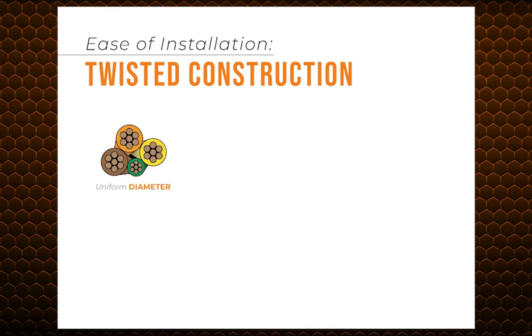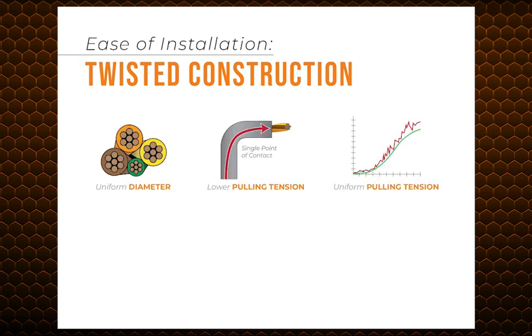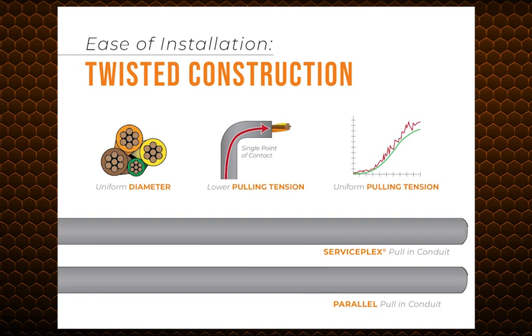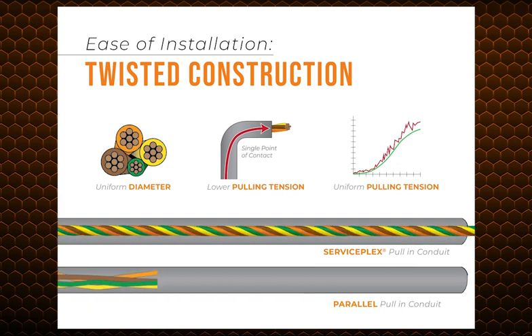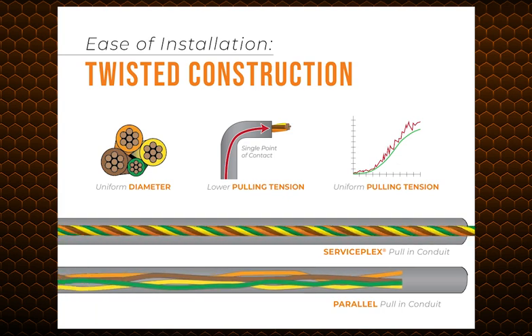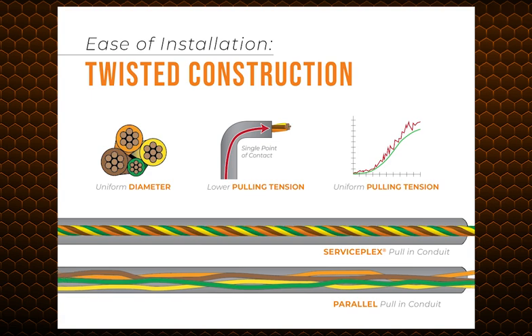ServicePlex has a uniform diameter for the overall cable, ensuring a consistent construction throughout. Unlike paralleling, the OD on our prefab solution eliminates jamming, making it easier to pull wire into the raceway or conduit. Because ServicePlex has a uniform outside diameter, less surface area comes into direct contact with the inner wall of the conduit during the pull, reducing the required pulling tension. This allows for easy pulls and faster installation. With less friction between the cable and the conduit, ServicePlex provides a more stable pull, resulting in lower pulling tension.